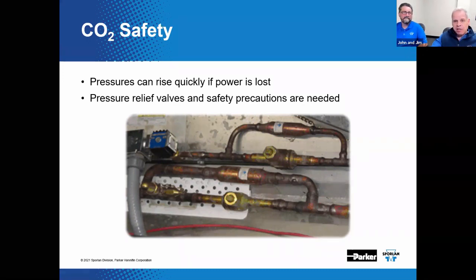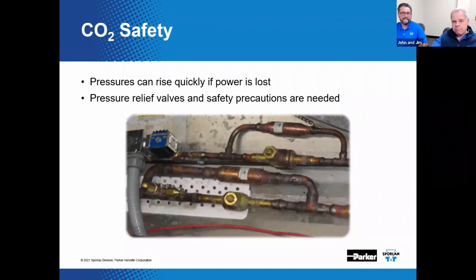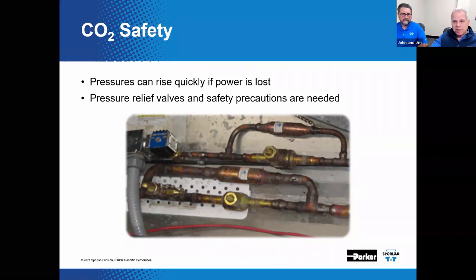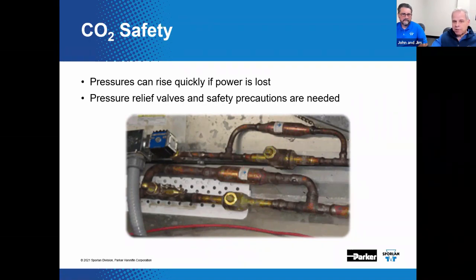Safety is a concern with CO2 systems due to this high pressure. If liquid refrigerant is trapped in a heat exchanger and allowed to warm up to even ambient temperatures, the pressure will increase and could cause injury or damage to equipment, systems, components, and humans, cats and dogs alike. Pressure relief valves are typically used to vent CO2 if the pressure rises to dangerous levels. In this example, you see check valves are piped around the ball valves to relieve pressure if refrigerant is trapped, causing the pressure to spike, which could be very bad because you don't want your supermarket to explode. No, we don't want those to explode, huh?